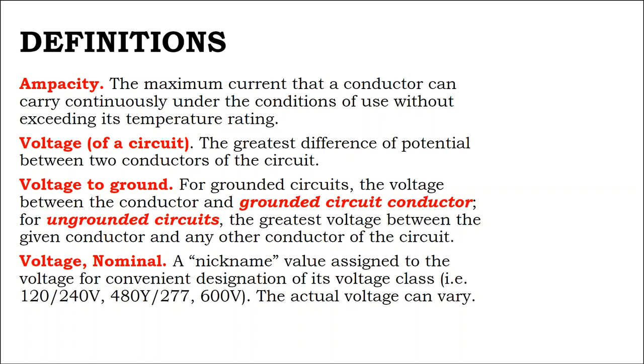Now, ampacity is not like that. Ampacity is that electrical flow through the current, and if it draws a little bit more current than what it's rated for, it'll heat up and start smoldering, kind of like a slow burn, unless the current is greatly exceeding the current requirement. Whereas voltage is like the skin of the cable, like the skin of the water balloon. Is it rated for the pressure of that circuit? Because if it's not, it'll just blow up. It won't heat up. It'll blow apart. Voltage is more like pressure. Ampacity is more like flow rate or flow.